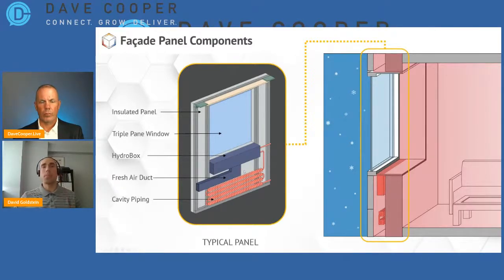The other detail worth mentioning is this ventilation air duct bringing fresh air to the hydro box - it's going to have a small tap that supplies a small amount of air into that cavity. That does two things: it pressurizes the cavity slightly to prevent infiltration of outdoor air, and since that ventilation air is fully conditioned, dehumidified air, if for whatever reason moisture sneaks into the cavity, we're continually drying it out. That's how we keep it dry and avoid any moisture issues.